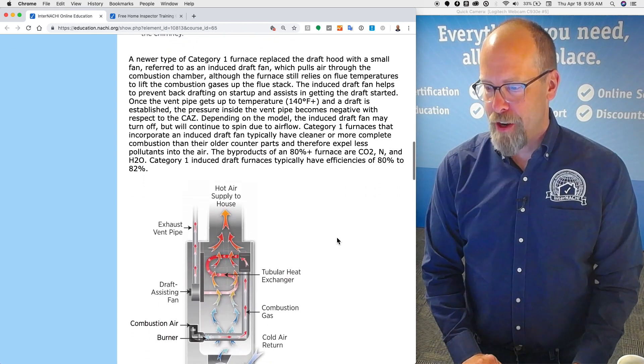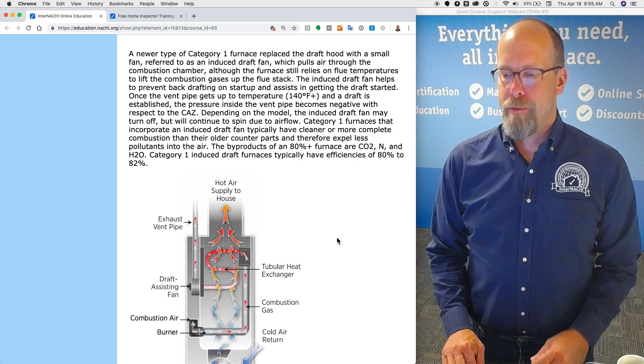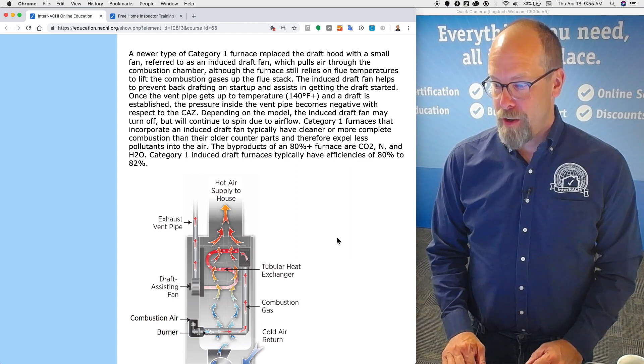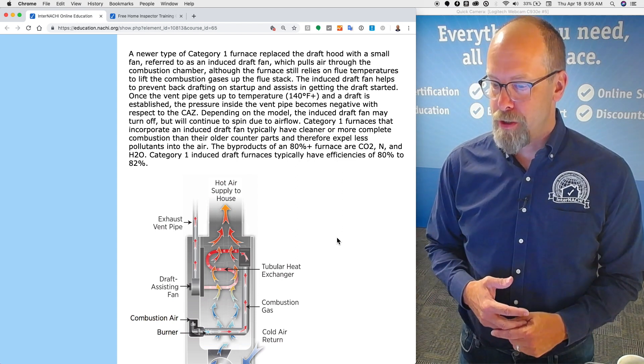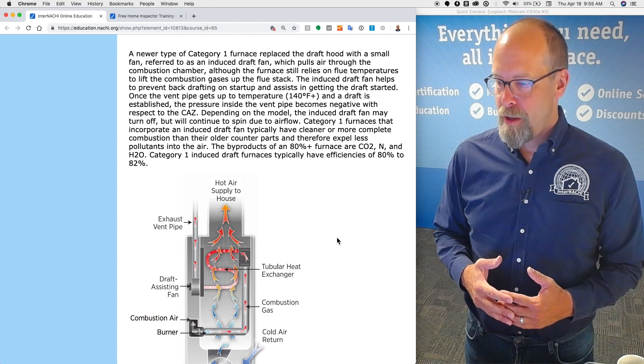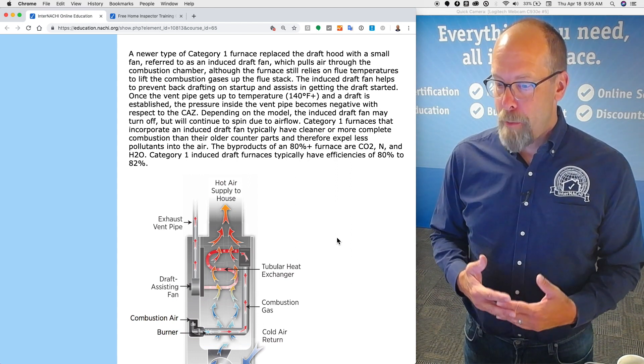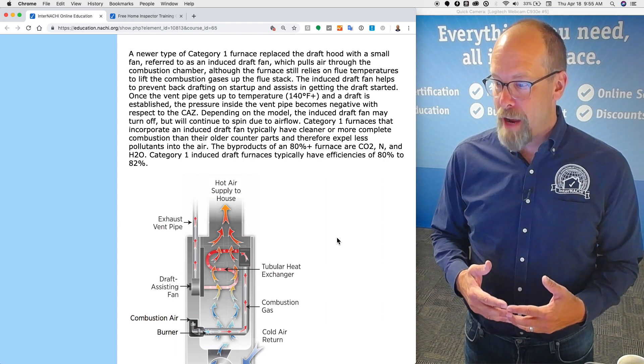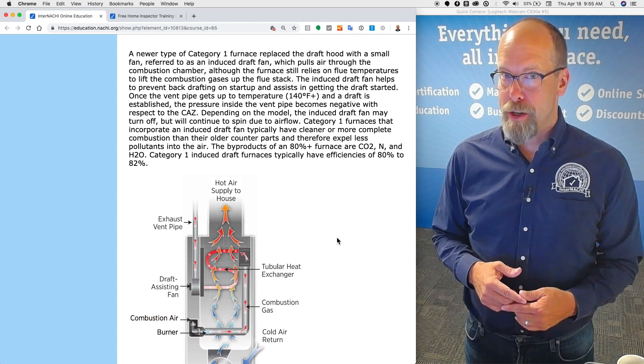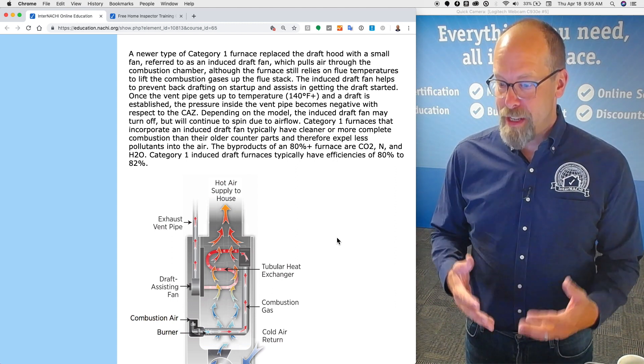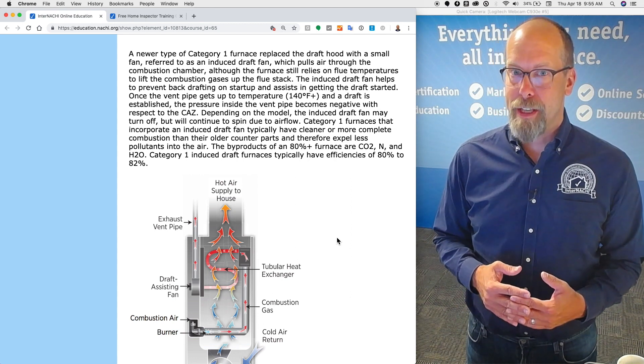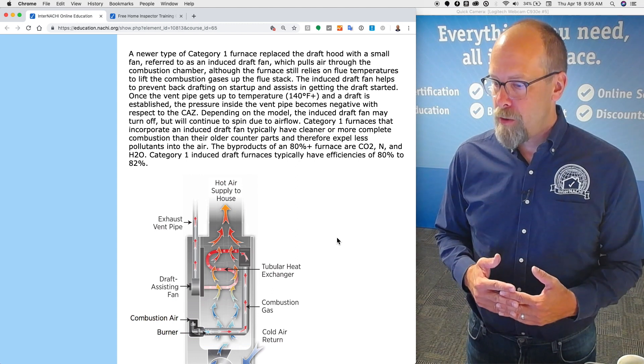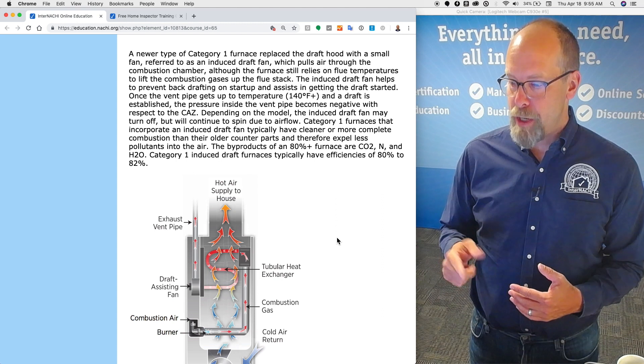A newer type of category one furnace replaces the draft hood with a small fan, referred to as an induced draft fan, which pulls air through the combustion chamber. Although the furnace still relies on flue temperatures to lift the combustion gases up the flue stack, the induced draft fan helps to prevent backdrafting on startup and assists in getting the draft started. Once the vent pipe gets to a certain temperature, greater than 140 degrees Fahrenheit, and the draft is established, the pressure inside the vent pipe becomes negative with respect to the CAZ.